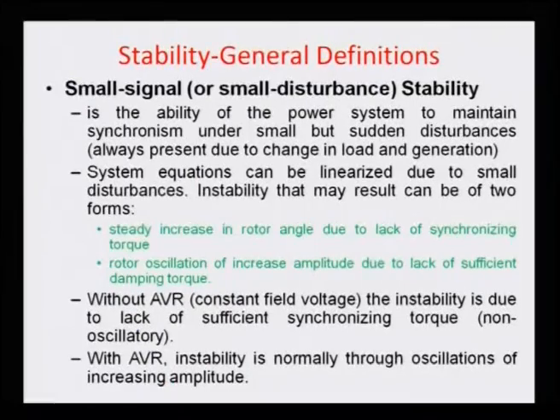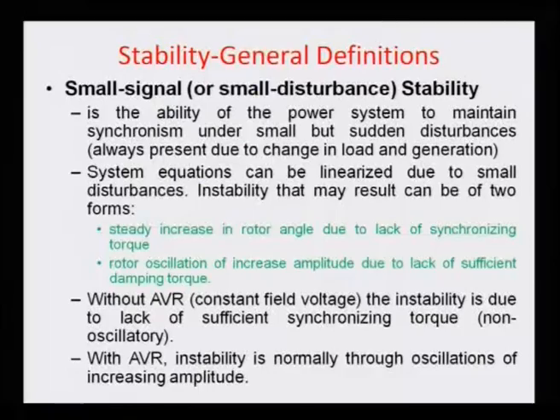We can analyze this whole scenario using two cases: without automatic voltage regulators, AVR, and with AVR. Without AVR means the field voltage is constant—there is no automatic voltage regulation, so the field excitation is constant, and the instability is due to lack of sufficient synchronizing torque, which is always non-oscillatory.